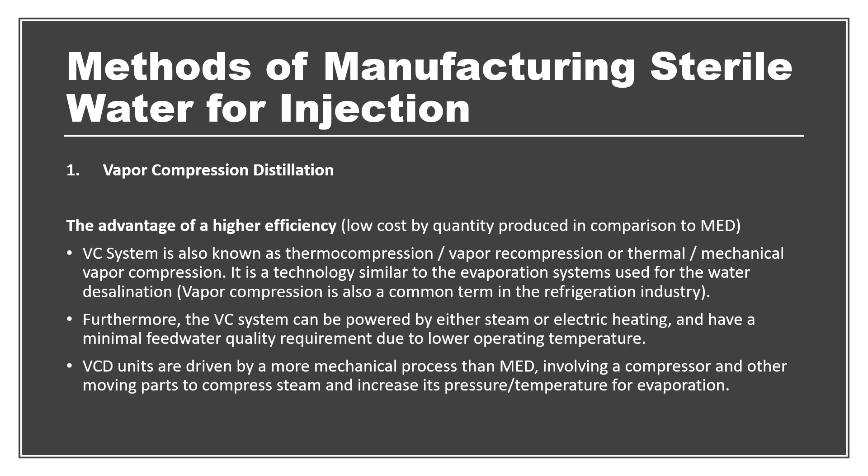Next we move to understanding the different methods for manufacturing sterile water for injection. Water for injection is generally prepared through steam distillation, where vapors are condensed and water is collected. At a commercial level, three methods are used. The first is the vapor compression distillation method, which is an advanced version of distillation where steam is vaporized, the vapors are collected and condensed, and pure water is formed.